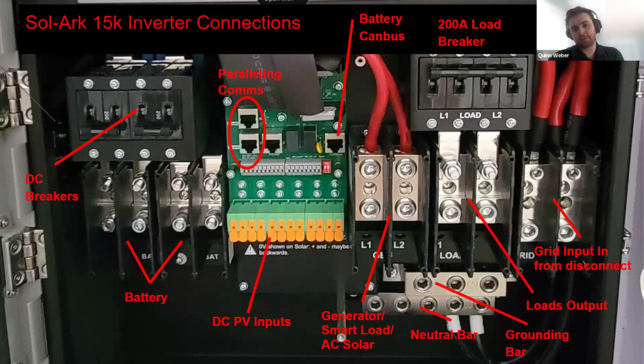We actually see that for customers who have existing solar systems, and then they want to retrofit and have a smarter inverter. So for instance, I personally did one in California where the customer had another company install a Sonnen battery system with a SolarEdge as their generation capacity for an off-grid system, and he had a 24 kilowatt Briggs and Stratton generator, and wasn't getting the power he wanted. It didn't really work well, and so we came in, AC coupled his existing SolarEdge system onto the AC side, ran the generator into the grid side, and his system worked beautifully after that. So there are applications where that can make sense.